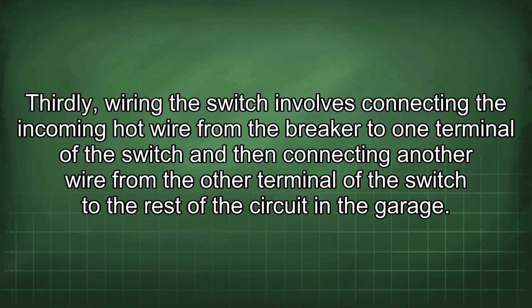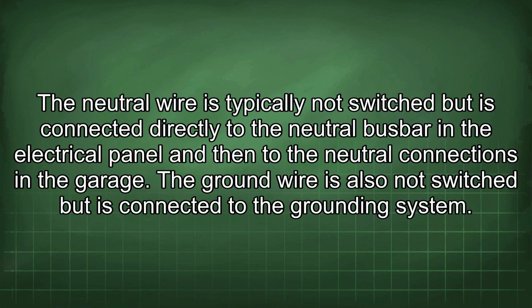Thirdly, wiring the switch involves connecting the incoming hot wire from the breaker to one terminal of the switch and then connecting another wire from the other terminal of the switch to the rest of the circuit in the garage. The neutral wire is typically not switched but is connected directly to the neutral busbar in the electrical panel and then to the neutral connections in the garage. The ground wire is also not switched but is connected to the grounding system.